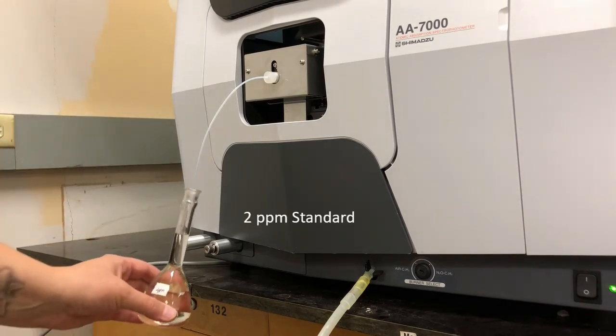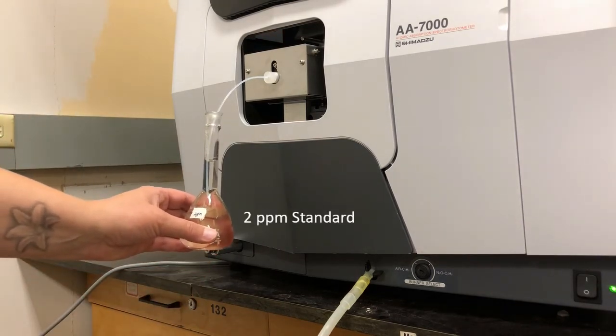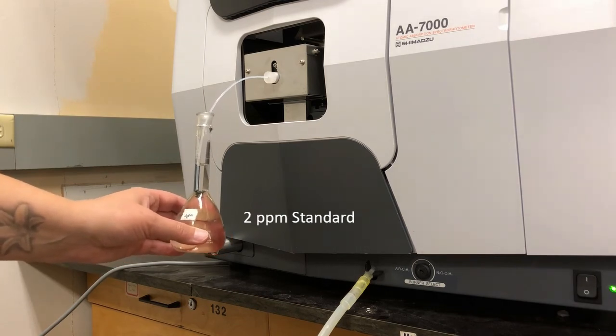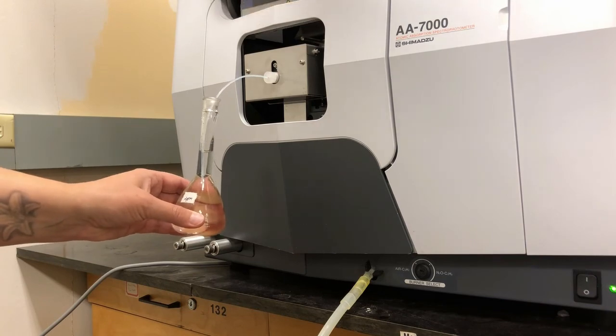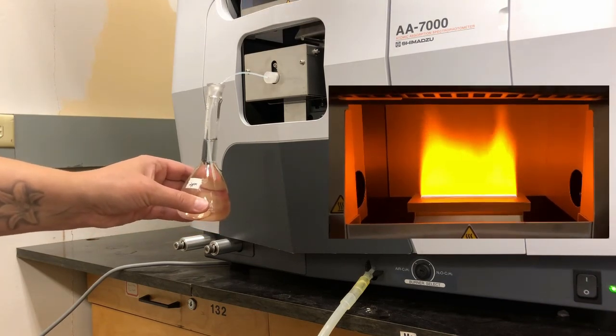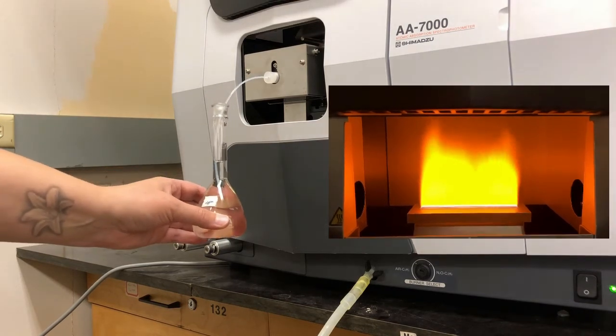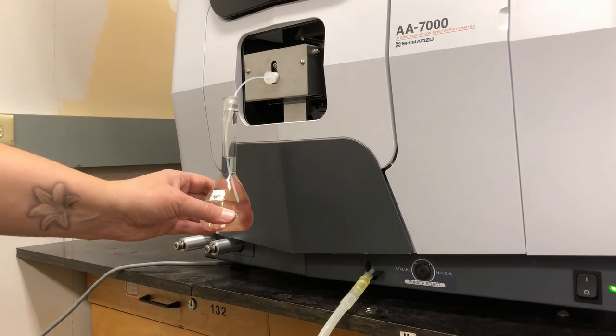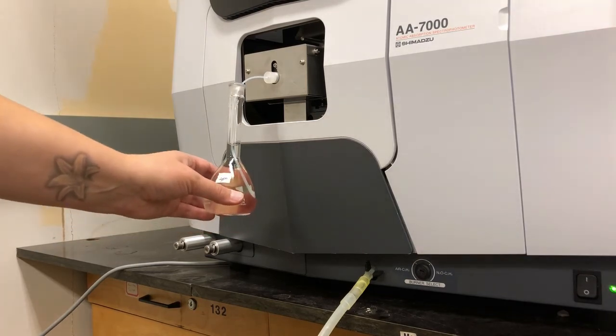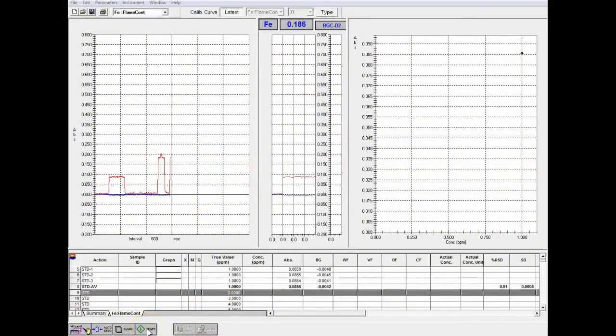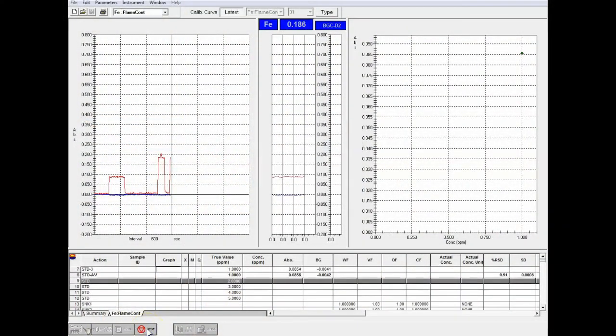Our next standard is 2 ppm, and you can see I'm just holding it under the sample tube so that it's taken up by the nebulizer. If I open this carefully, you can actually see the color change in the flame as the elements are entering the flame. We hold this in position, and then we hit start on the machine. You can see over here on our graph, this is just the raw data graph, but you can see the jump in absorbance, and that's expected because we just doubled our concentration, so went from 1 to 2.